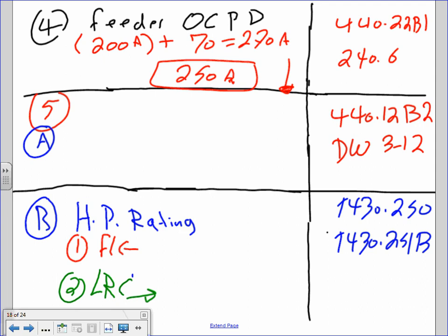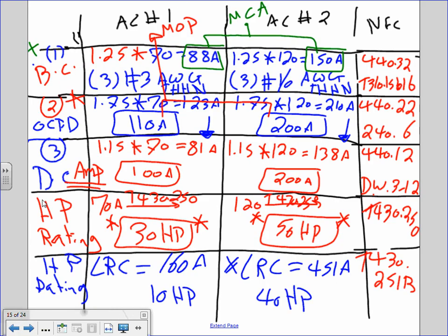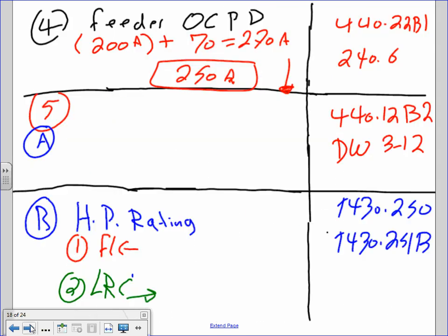The 200 came from the largest fuse in the system — that's the fuse for the branch circuit, not the disconnect. The largest branch circuit fuse was 200A; add the other motor's full load amp of 70A = 270A, then go down to 250A.